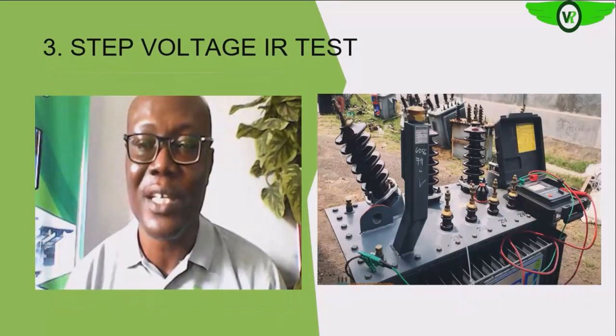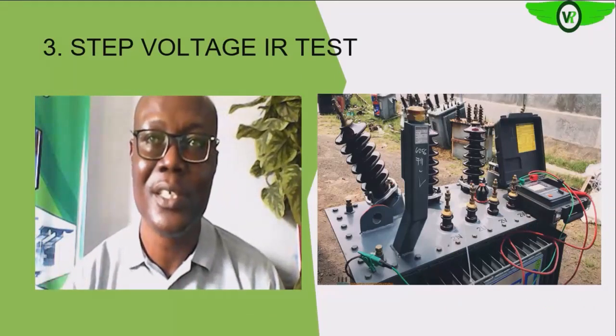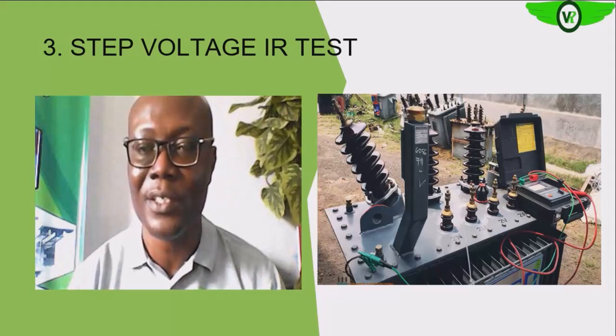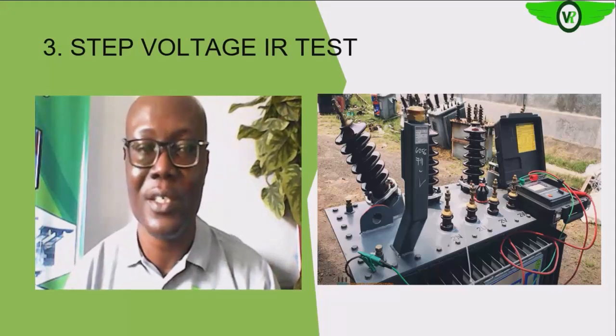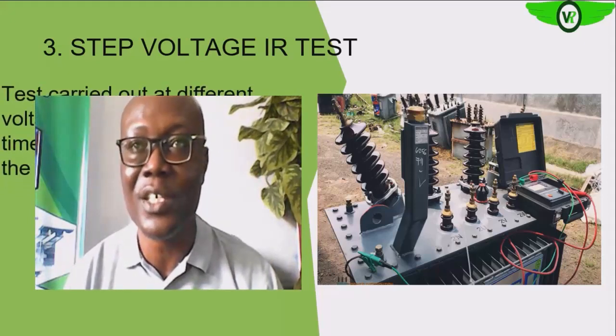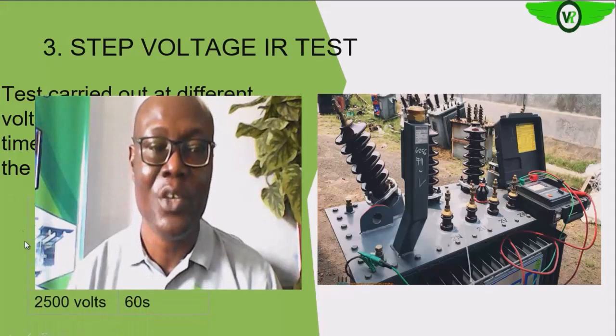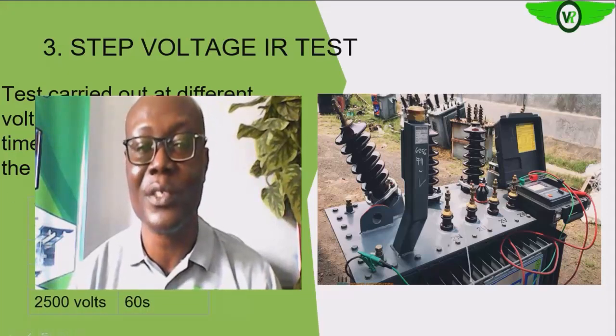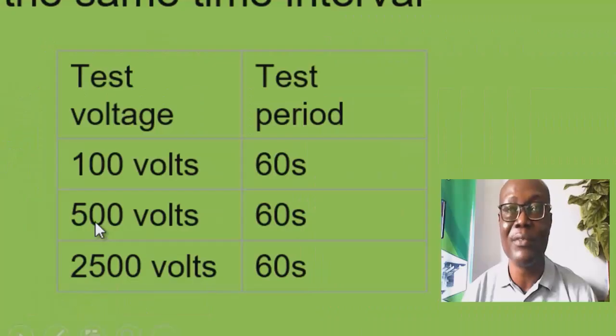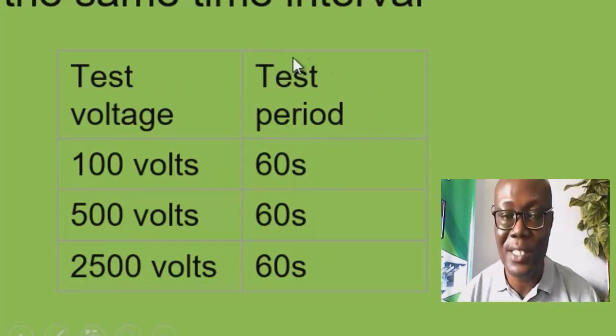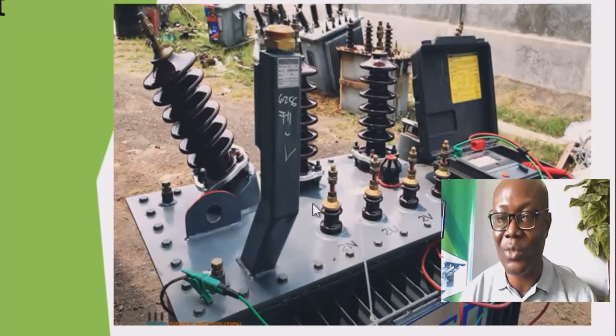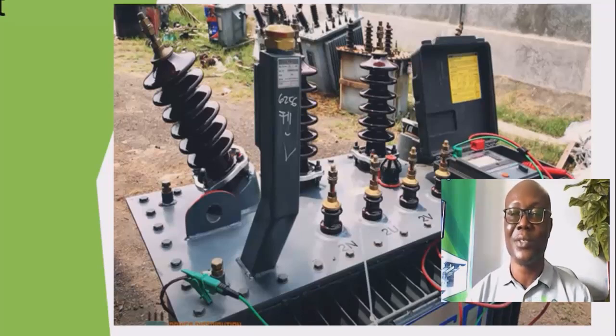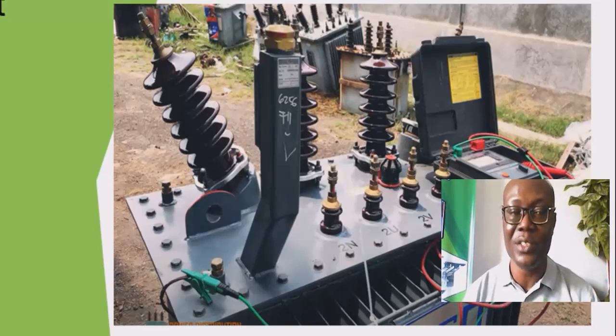So on the step voltage test, like we said earlier, you increase the voltage in steps that you inject into the system. But like we said, you do it in increments of 5 times the original test voltage. So as you can see here, if you inject 500 volts for 60 seconds, the next test voltage will be 2500 volts for another 60 seconds. Assuming you are testing any of the windings, maybe secondary winding to ground, as you have here now, you carry out the test in these steps. So as you increase it, you inject, you increase it, you inject, and take your readings.